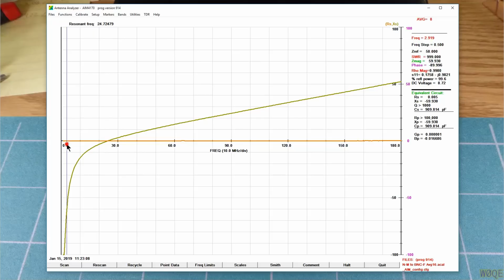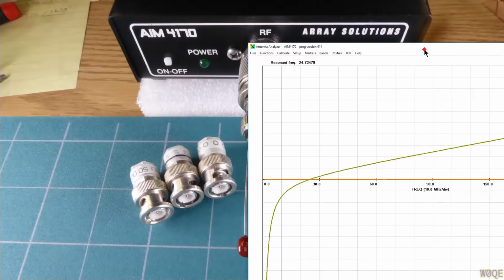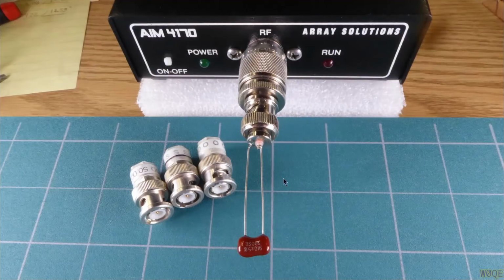If we measure the capacitance down here at low frequencies, we see it around 900 picofarads, which is what we would expect. At 10 megahertz, we see the value being 1,078 picofarads. So this begs the question: is there something wrong with my analyzer? Something wrong with my calibration? Something wrong with my test setup? Or I just don't understand what's going on? Well, the answer to that's pretty clear. What's going on, at the very least, is the fact that we did not compensate for these leads.